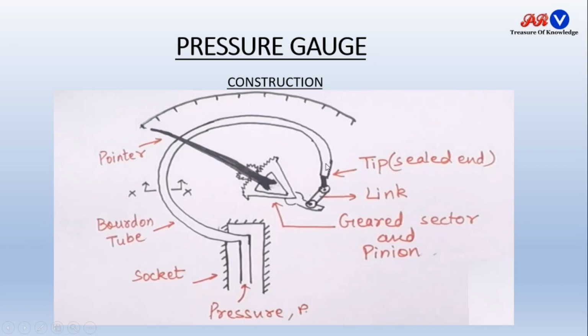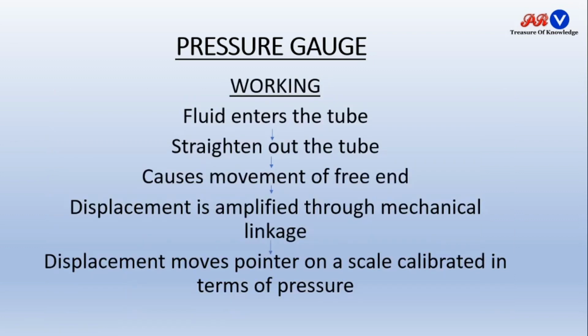This is the link. Whenever some displacement of this tube occurs, this link will amplify displacement and give that displacement to the geared sector and pinion arrangement, which moves the pointer on the scale, and in this way applied pressure produces some displacement, and this displacement is converted into pressure to show on the scale. This is the working of the C-type tube.